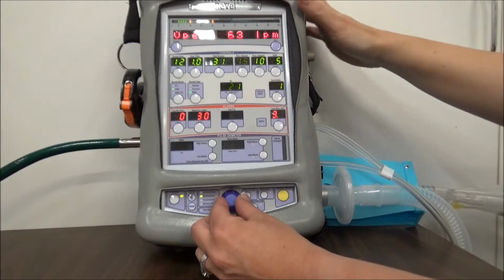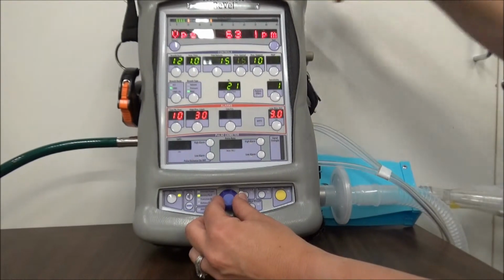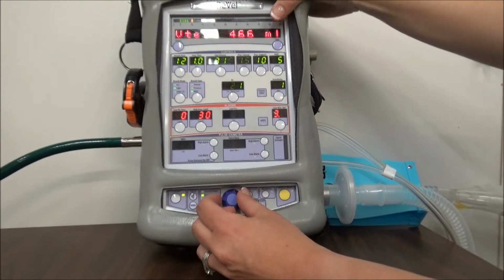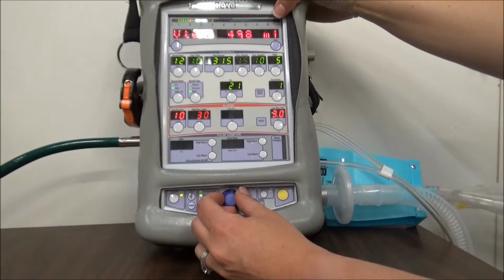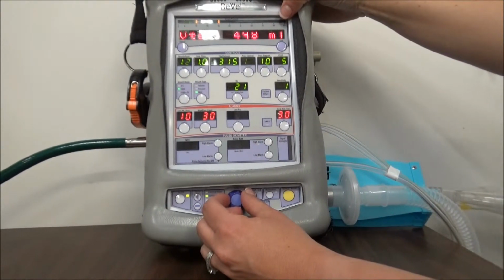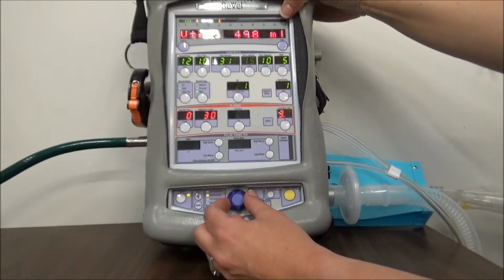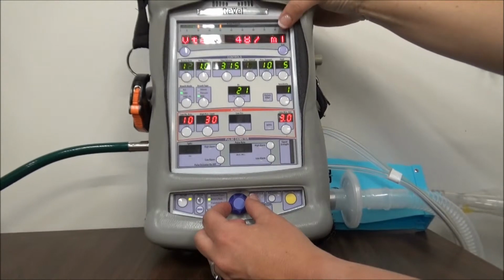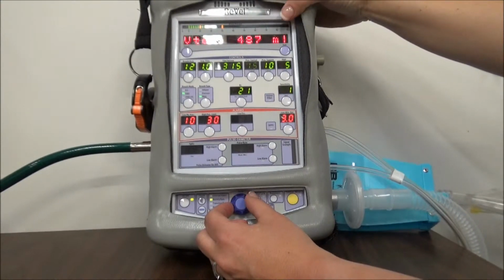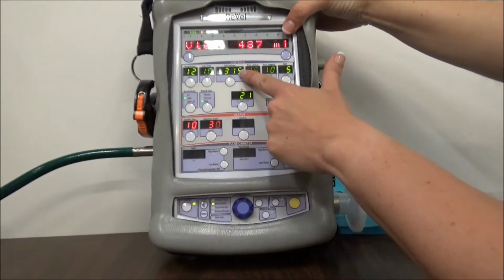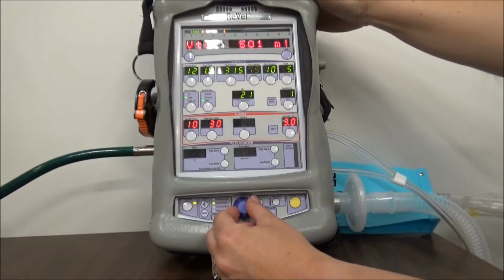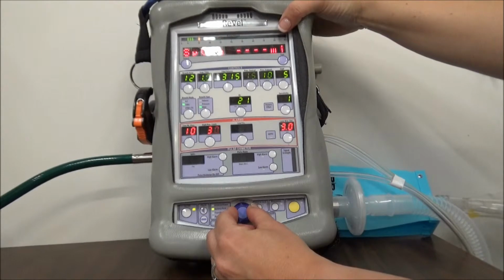This is your peak flow. This is what is going through your circuit right now in order to deliver the tidal volume that you need. And then here's your VTE, that's your exhaled tidal volume. We talk a lot about this number, especially when we're in pressure mode, so when we're in pressure control and we're in non-invasive modes, this is how we determine a lot of things. So you're putting in 315, this is what the patient's putting out, meaning they're entraining a little bit more tidal volume for you. That's important to know.